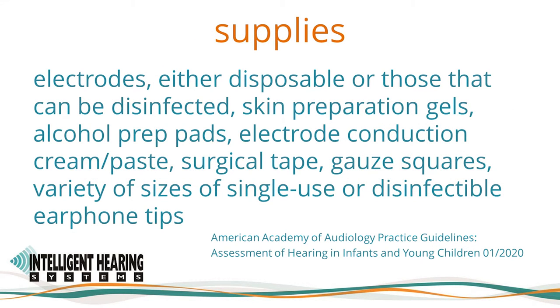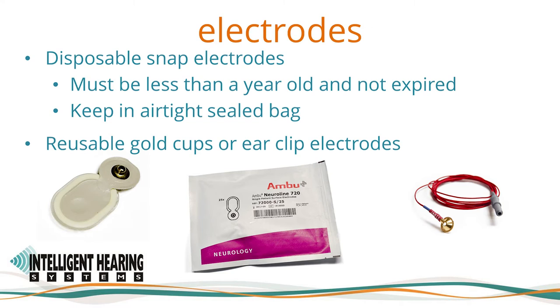The supplies you will need include electrodes — either disposable or those that can be disinfected — skin preparation gels, alcohol prep pads, electrode conduction creams or pastes, surgical tape, gauze squares, a variety of single-use or disinfectable earphone tips, and an otoscope and specula. Disposable electrodes are recommended for infection control. IHS has validated the equipment with the Ambu Neuroline disposable electrodes. Be sure that disposable snap electrodes are kept in an airtight sealed bag, are less than a year old, and are not expired. The electrodes are pre-gelled and should not be dry; fresh electrodes will have gel on the center sponge.